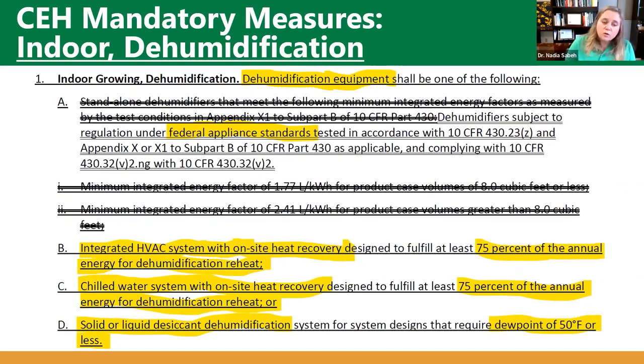If you have a chilled water system, same idea - they want 75% of the heat recovered, or 75% of the reheat used for dehumidification to come from heat recovery. That could be if you had a cogen system, a heat recovery chiller, or some other process generating waste heat. They want us to recover that to provide 75% of the heating.